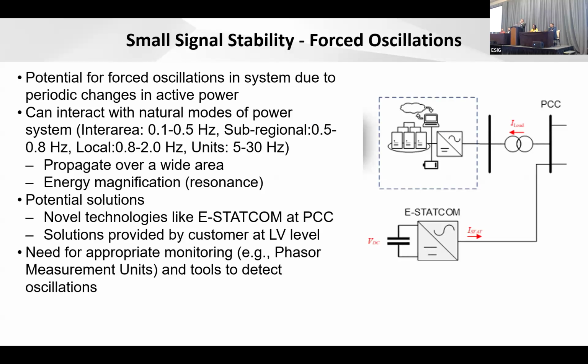So this frequency injection signal, this low frequency injection signal, is going to be there all the time. You need to be careful that this frequency doesn't match any of the natural modes. If there are any nearby units, they have torsional modes, so you need to stay away from those, as well as your local area modes, sub-regional modes, and the worst case, the inter-area modes. I say worst case because inter-area modes, the lower the frequency, the further away it travels.